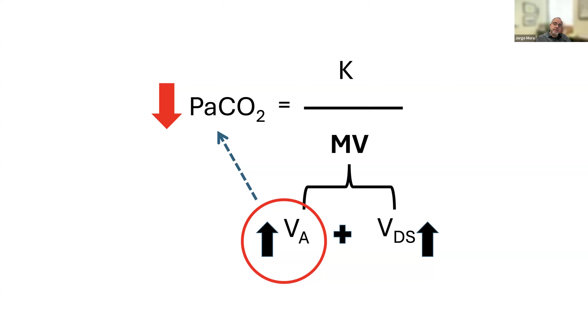Non-invasive ventilation and a stenting of the airway imply, quote unquote, injecting air into the respiratory system using positive pressure. The big difference between invasive and non-invasive ventilation is that things are more steady and more measurable when we use invasive ventilation, because it's a closed circuit to start with. In non-invasive ventilation, even though you can have active circuits, most of the time we use passive circuits where the exhalation and the release of CO2 out of the system occurs passively through leaks in the system.